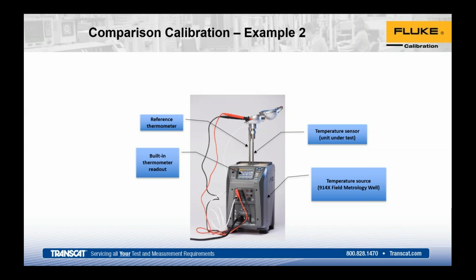So instead of relying on the internal control sensor of the dry well, we're now bumping up to an external probe that's going to have a much higher level of calibration or lower uncertainty. So again, you're building upon your overall uncertainty. Instead of calling the display true temperature, now we're going to call the reference temperature true temperature. The display then becomes like your nominal set point. So again, just building on the next step.